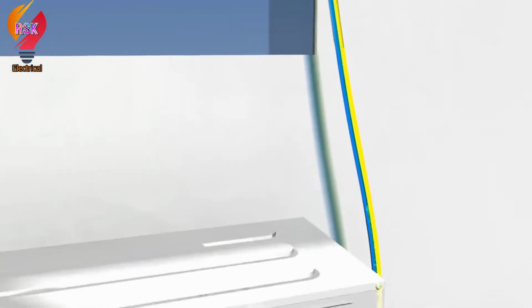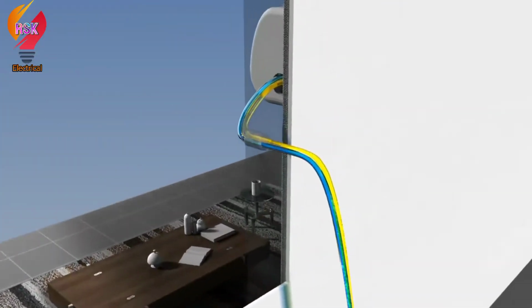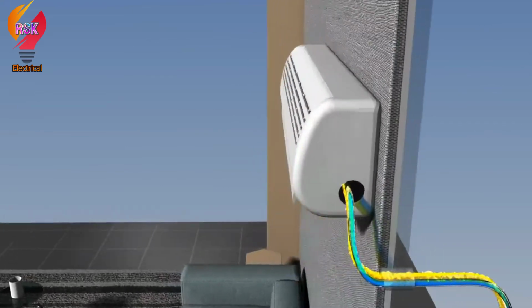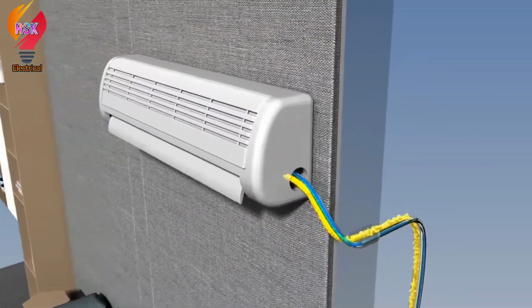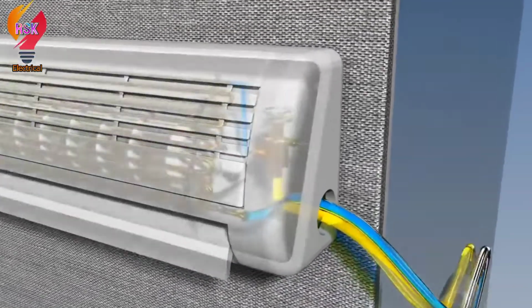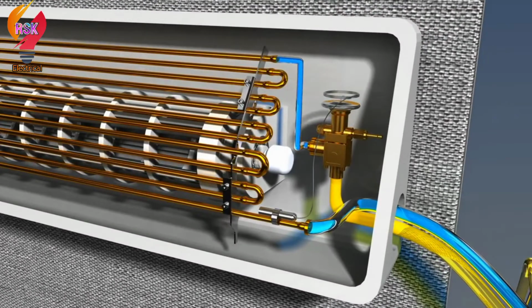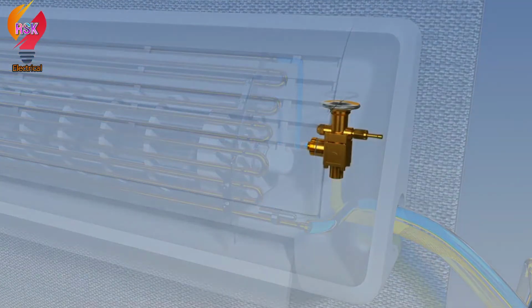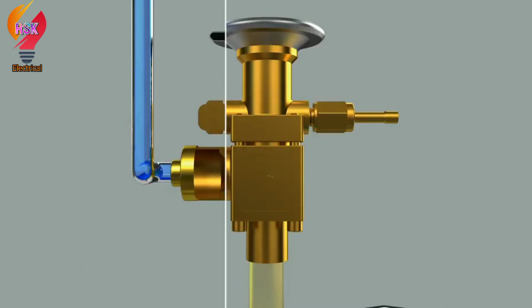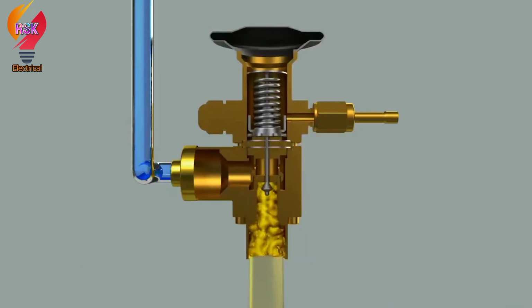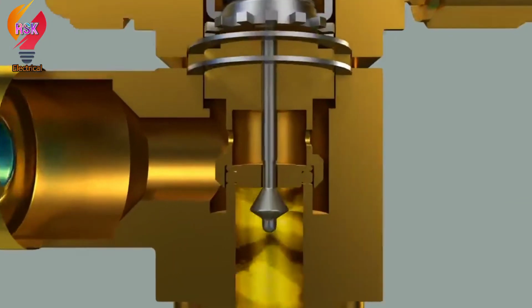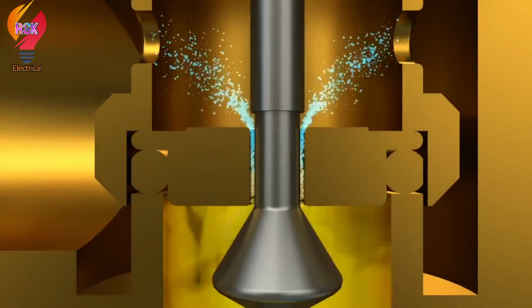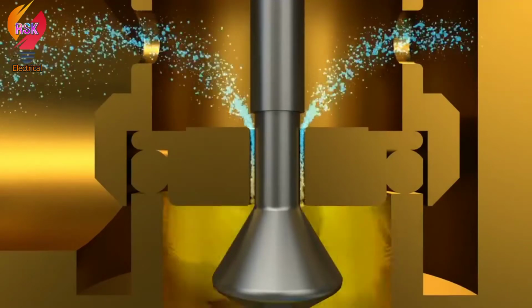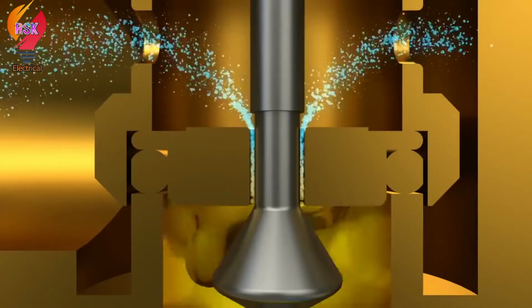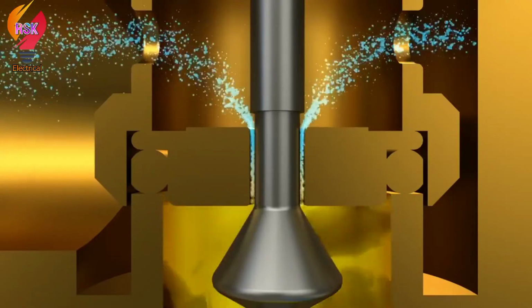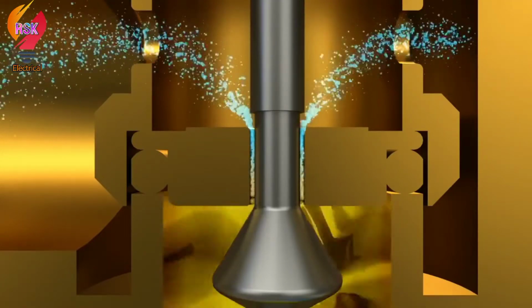Although the refrigerant has thrown off some of the heat as it passes through a condenser, it is still hot, with a temperature of about 50 Celsius. The refrigerant in high temperature and high pressure liquid flows into the expansion valve. The refrigerant which used to flow in a large space now passes through a narrow area, and its pressure drops as it goes. When the pressure drops, temperature drops dramatically as well. The cool refrigerant is now sent to an evaporator.